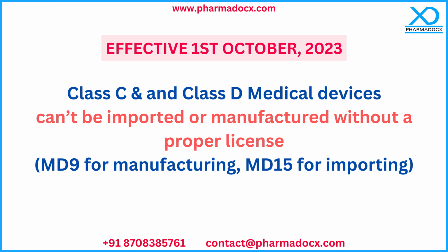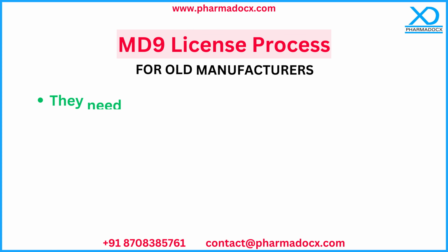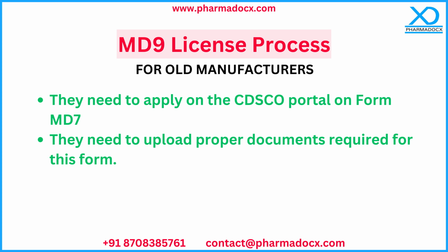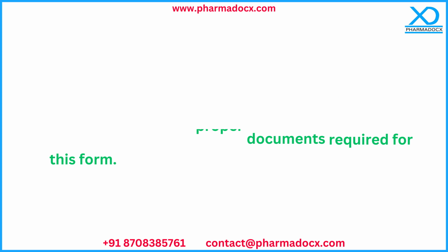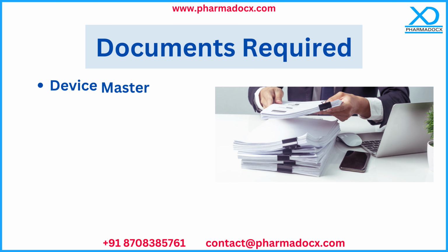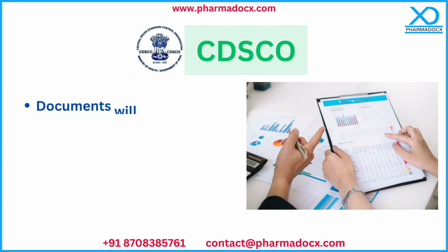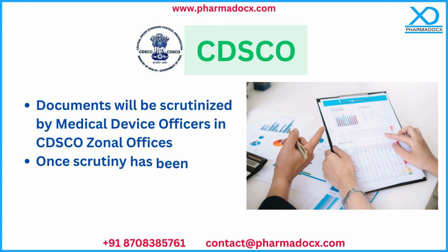The process for obtaining an MD9 license for the old manufacturers in India is simple. They need to apply on the online CDSCO portal on Form MD7. Certain documents such as the device master file, plant master file, quality management system, along with some legal documents such as the rent agreement or company incorporation documents need to be submitted on the online CDSCO portal. The documents will be scrutinized by the medical device officers in CDSCO zonal offices.